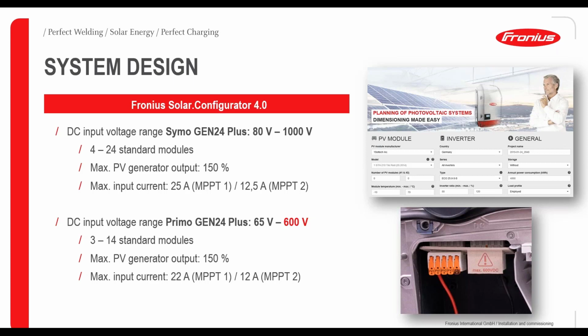The same goes for the Primo Gen24. It even starts at a lower range of 65 volts. But here is the big difference: the Primo Gen24 is not a 1000 volt device. So please make sure not to put more than 600 volts, which is the maximum the device is able to handle on the DC side. Otherwise, it would be destroyed. So please make sure to dimension it right, and therefore, again, please use the Fronius Solar Configurator.